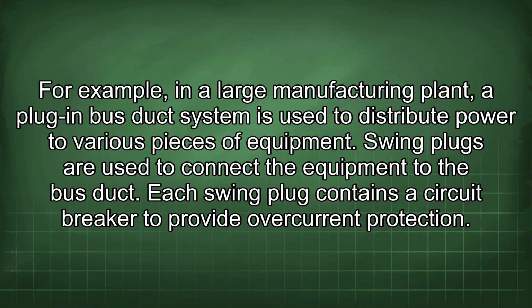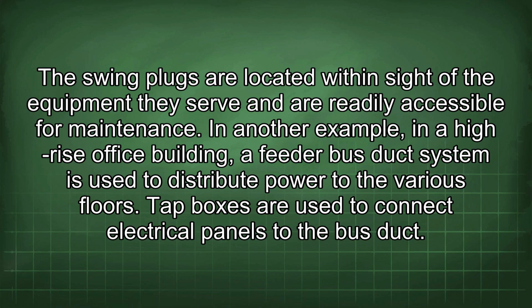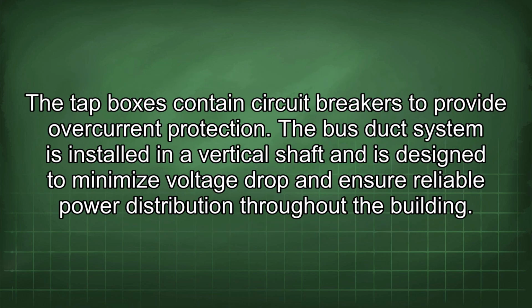For example, in a large manufacturing plant, a plug-in bus duct system is used to distribute power to various pieces of equipment. Swing plugs are used to connect the equipment to the bus duct. Each swing plug contains a circuit breaker to provide overcurrent protection. The swing plugs are located within sight of the equipment they serve and are readily accessible for maintenance. In another example, in a high-rise office building, a feeder bus duct system is used to distribute power to the various floors. Tap boxes are used to connect electrical panels to the bus duct. The tap boxes contain circuit breakers to provide overcurrent protection. The bus duct system is installed in a vertical shaft and is designed to minimize voltage drop and ensure reliable power distribution throughout the building.